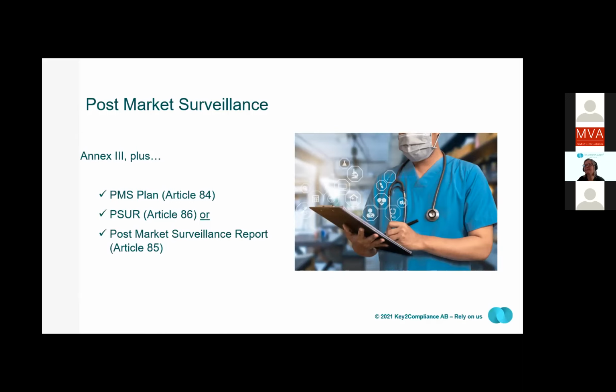The technical documentation needs to include a post-market surveillance plan, and for Class 2A, 2B, and 3 devices, a periodic safety update report, and for Class 1 devices, the post-market surveillance report. Manufacturers of Class 2B and 3 devices need to update their periodic safety update report at least annually.